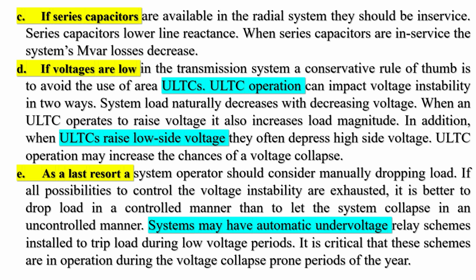As a last resort, a system operator should consider manually dropping load. If all possibilities to control the voltage instability are exhausted, it is better to drop load in a controlled manner than to let the system collapse in an uncontrolled manner. Systems may have automatic undervoltage relay schemes installed to trip load during low voltage periods. It is critical that these schemes are in operation during the voltage collapse-prone periods of the year.